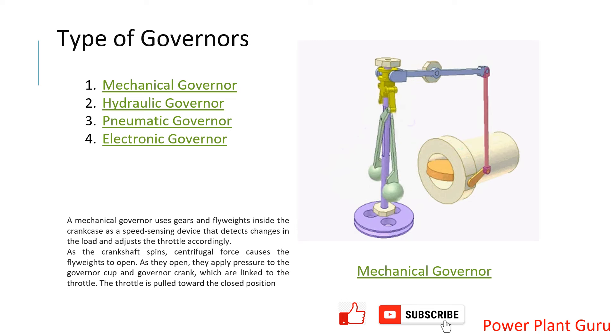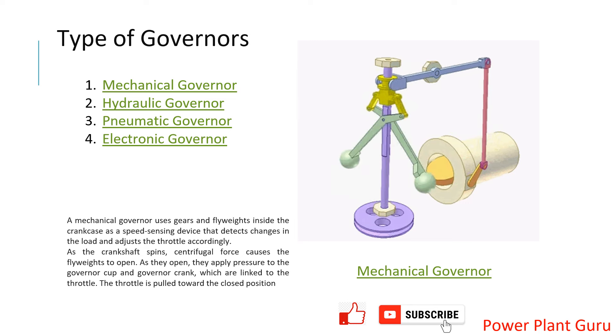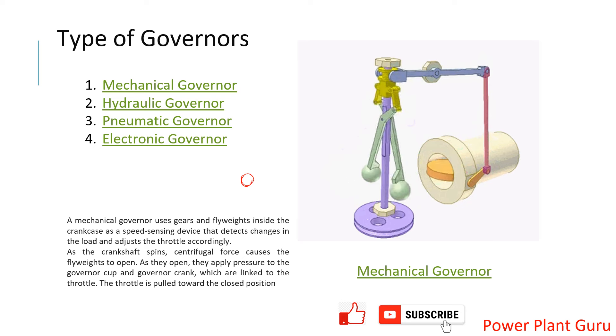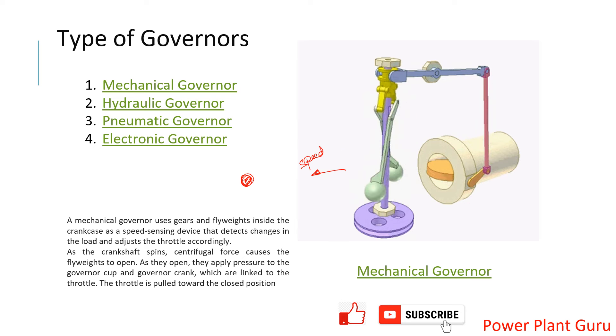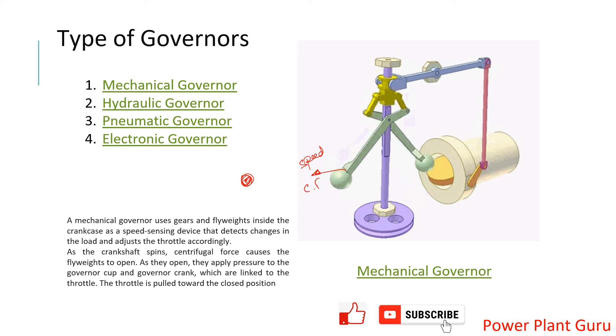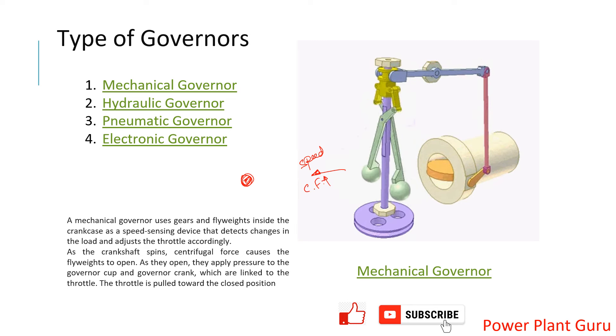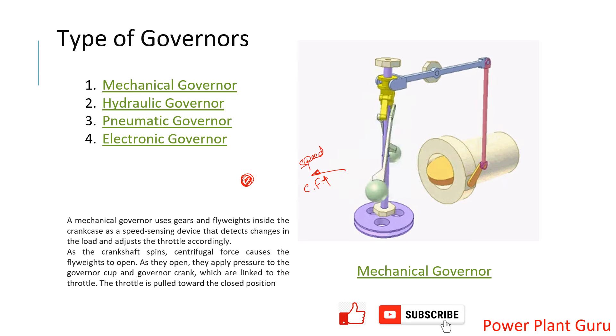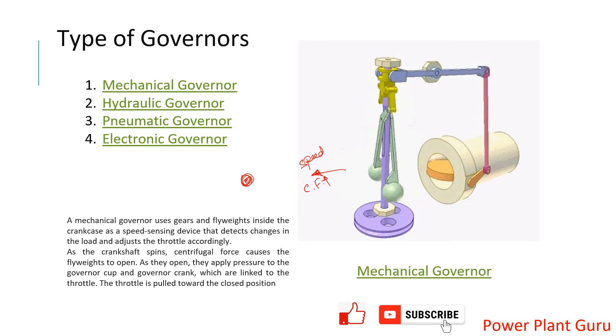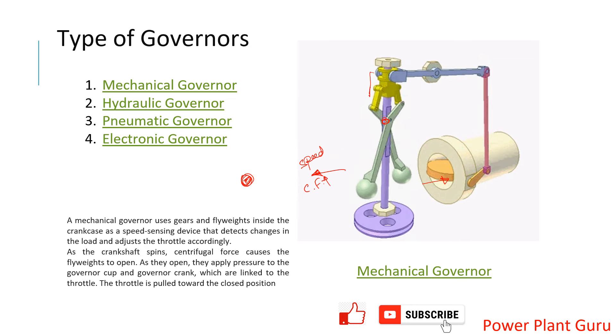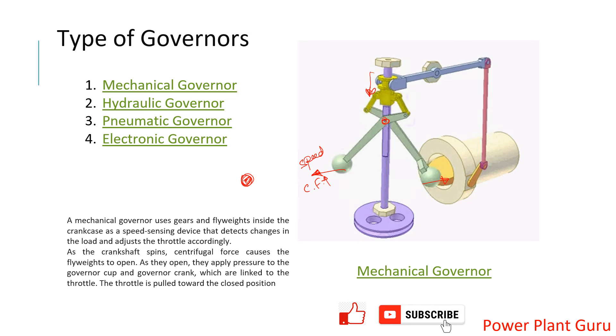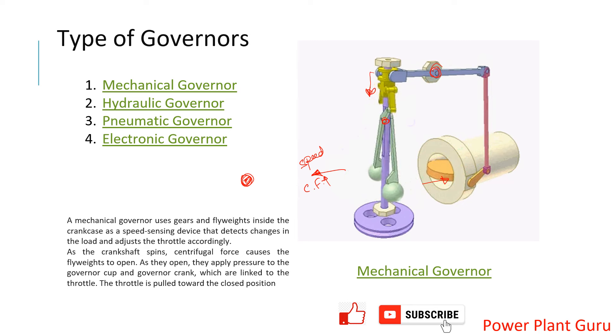You can see these two fly balls — the circular ones have metallic ball weights. When the RPM increases, centrifugal force increases, and that causes the fly balls to move outward in both directions. This movement acts against the spindle, causing the sleeve to move down.